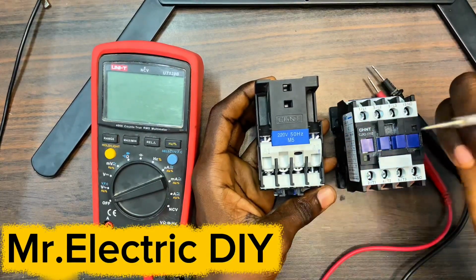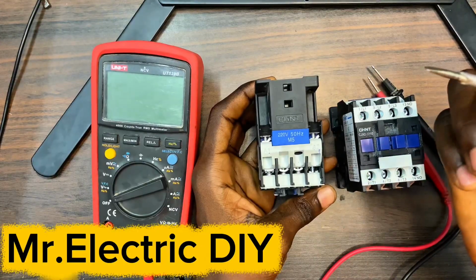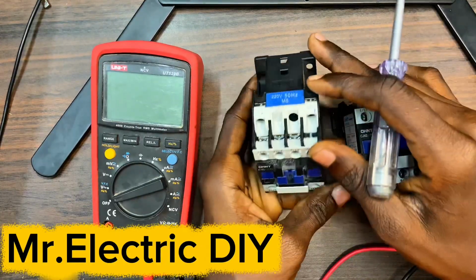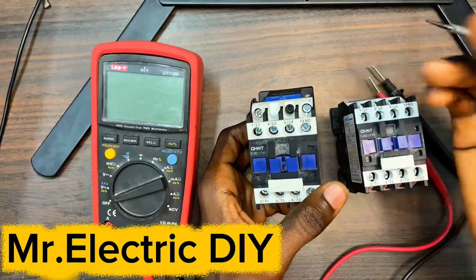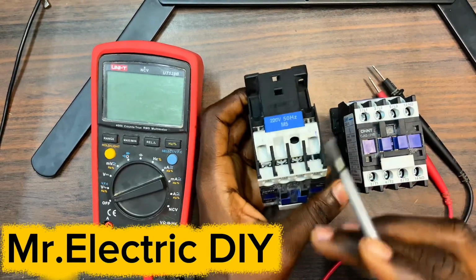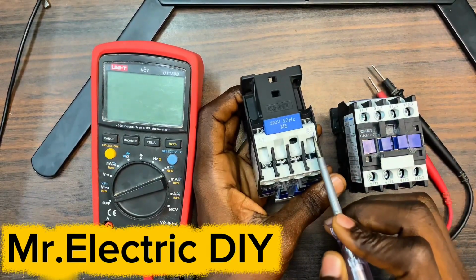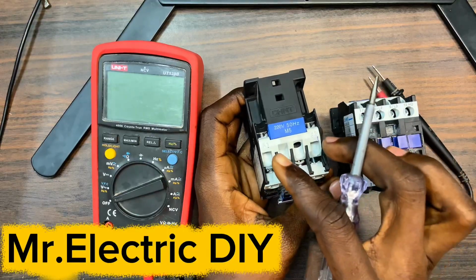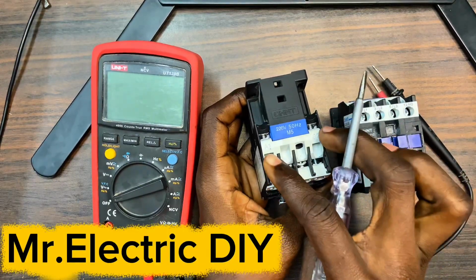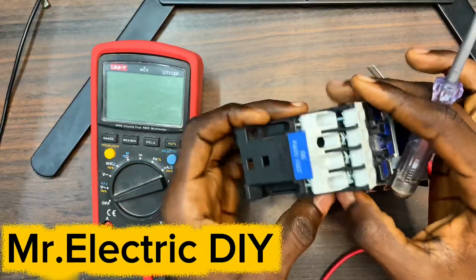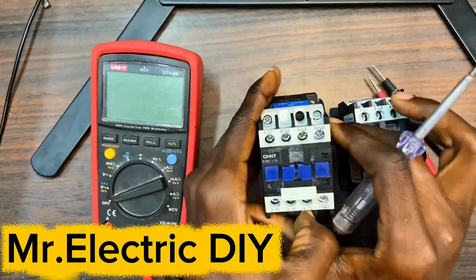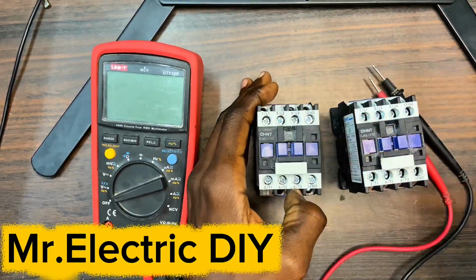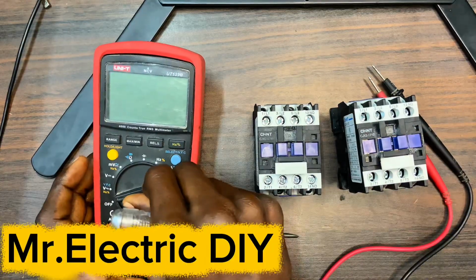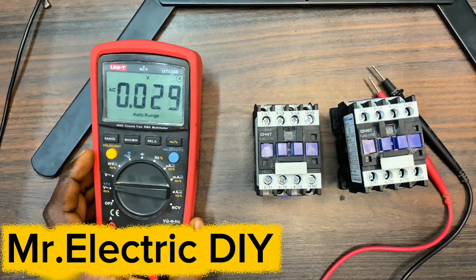So when you turn on the switch or push the push button, and this contactor is not energizing, it's not turning on, you have to first of all come straight to this A1 and A2 to check the voltage and also the ohmic value of the coil. We have a coil inside this magnetic contactor. So first of all, what I will do is to turn it to voltage.